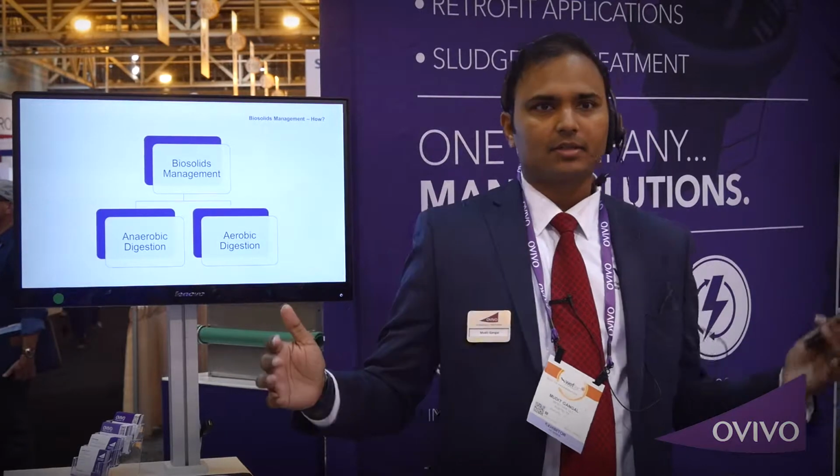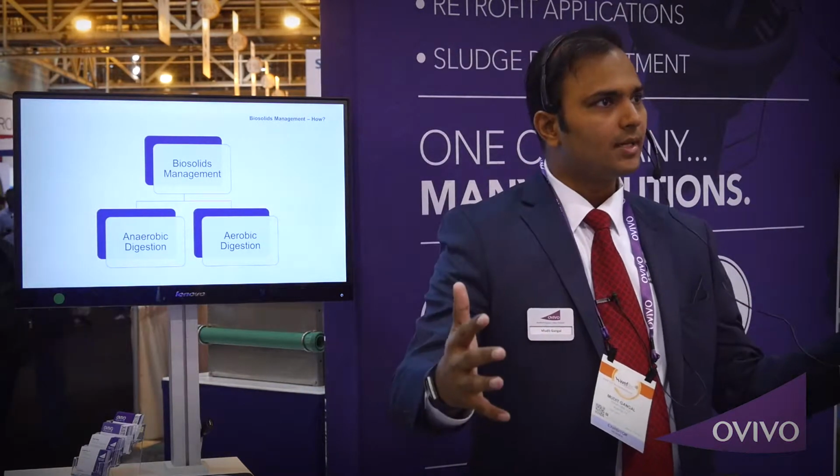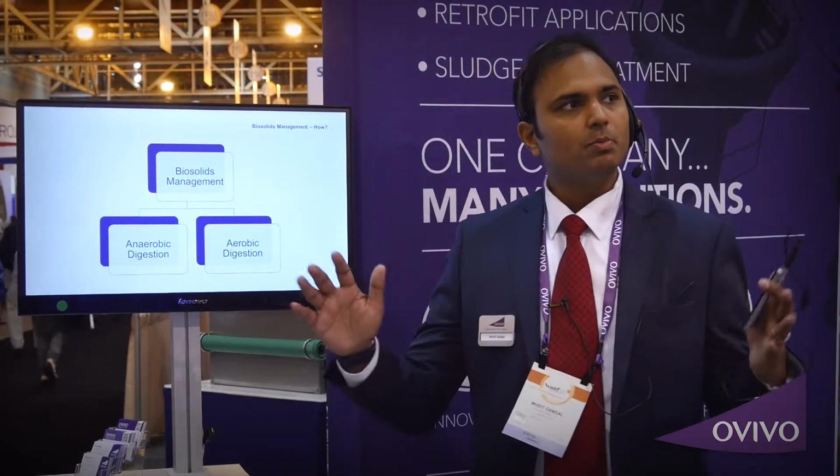So biosolids management, as to how do we accomplish it, there's two broad categories. There is anaerobic digestion and aerobic digestion. Anaerobic digestion is essentially treating the biosolids or the sludge that's produced in digesters under anaerobic conditions, so conditions without air. Basically you try to hold the biosolids inside these digesters for an extended period of time, where the different types of bacteria act on it and convert the organics and the cellular biomass into biogas. The other approach is aerobic digestion, where you take the sludge into aerated tanks, and essentially you use different types of bacteria to oxidize the sludge components and get your volatile solids reduction as a result of that. So those are two broad categories.